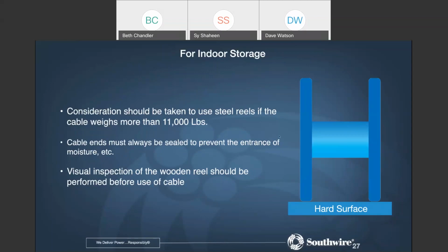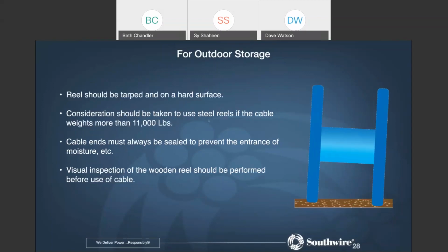Now, the thing about steel reels, I have to tell you, the reason it's not that popular is because you're going to have to pay a deposit on it. We take a deposit, and when you ship us back the reel, obviously you get it back. So that's the sticky thing about steel reels, but obviously there is a really good reason for steel reels. If you store them outdoors, this is not what you want to do. You really want to store them on gravel that's been tamped, that is a little hard, so the reels don't sink, because if the flanges sink, you're going to be resting on the cable. Obviously, you don't want this kind of behavior.